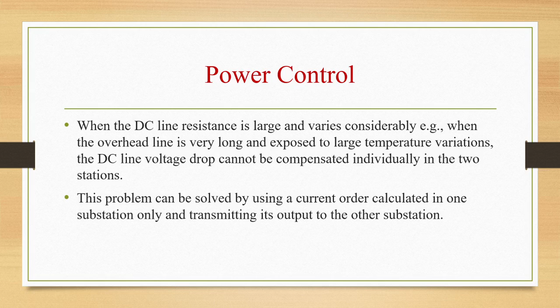So when the DC line resistance is large and varies considerably, for example when the overhead line is very long and exposed to large temperature variations, DC line voltage drop cannot be compensated individually in the two stations. This problem can be solved by using a current order calculated in one substation only and transmitting it to the other substation.